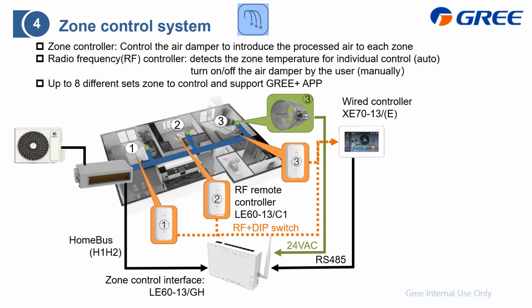First we need to register this RF remote controller to this one, and then also do the commissioning, which means building up the relationship between the RF remote controller and the air damper to make it 1-to-1. Then you can control the air damper. When it requires cooling, you can turn on the air damper to introduce the air. And also you can pick a different setting temperature, which means we can satisfy all rooms' temperature requirements, even if they are different.